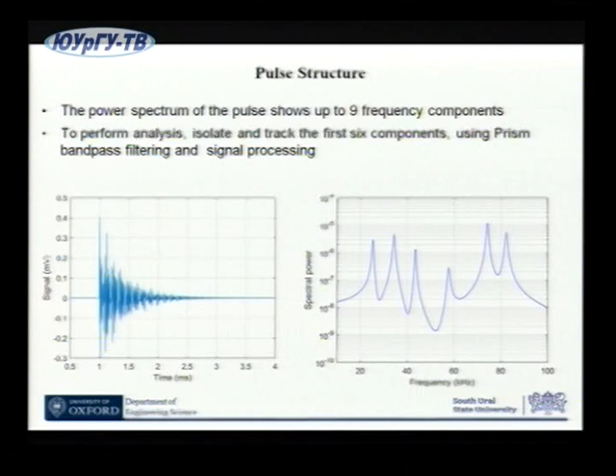If you look at that signal in more detail, what you have is multiple modes of vibration inside the housing, where each one decays over time, and where amplitude, frequency, and decay information provides diagnostics. So what we've been doing is applying PRISM signal processing, the bandpass filtering I was talking about.